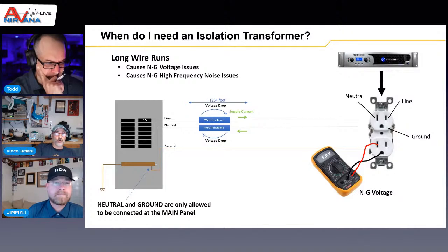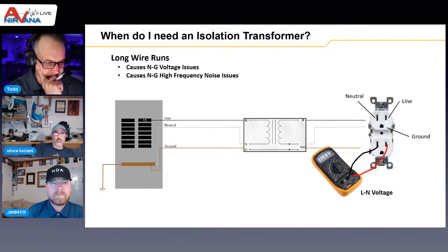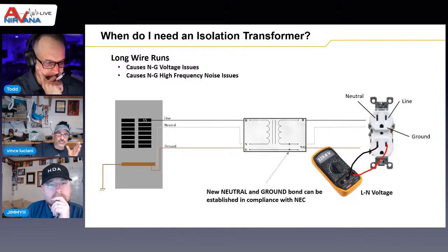So what can you do about it? I'm not going to move the breaker panel, and even if I did, I'd still have the same problem. You can put in an isolation transformer. When you include an isolation transformer, it allows us to legally, conforming to the National Electric Code, establish a new neutral-to-ground bond.